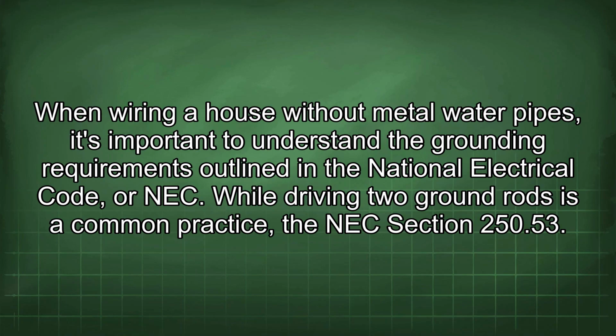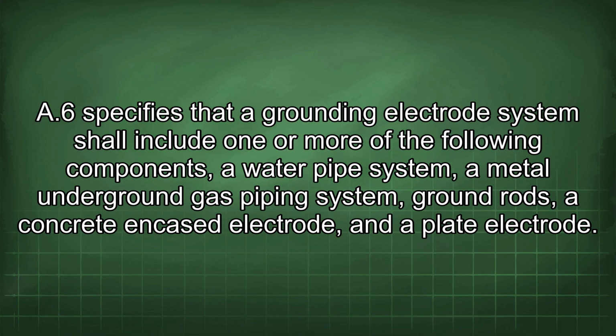When wiring a house without metal water pipes, it's important to understand the grounding requirements outlined in the National Electrical Code, or NEC. While driving two ground rods is a common practice, the NEC section 250.53 A6 specifies that the grounding electrode system shall include one or more of the following components: a water pipe system, a metal underground gas piping system, ground rods, a concrete encased electrode, and a plate electrode.